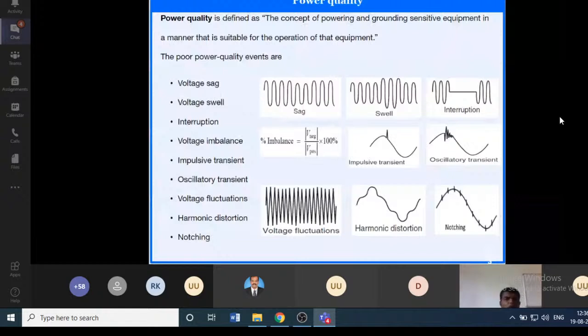When you go for power electronics devices, that will introduce high harmonic distortion. When you have harmonic distortion in the system, it will produce more heat in the machines. What are the machines we are using in electrical applications? That more heat is not good for the electrical machine life, right? Another one is notching. Notching is a periodic disturbance occurring in the system, usually caused by line commutated power electronic devices.